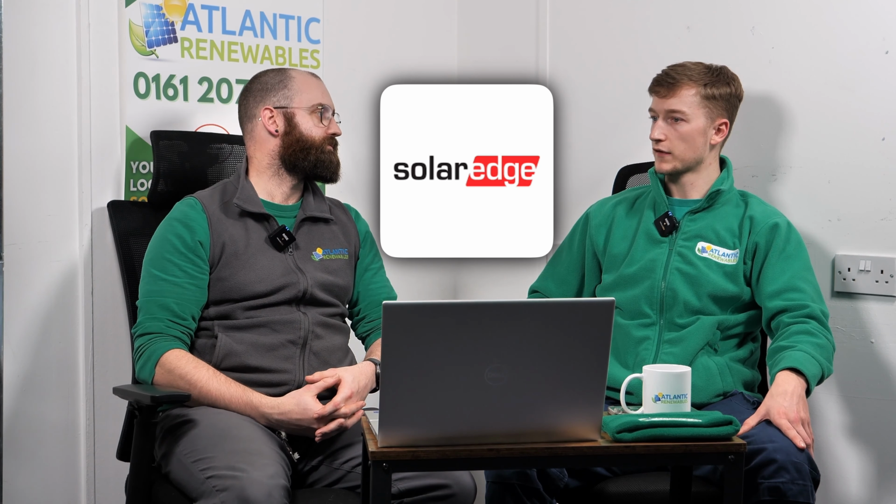I prefer the SolarEdge system. Definitely, if you've got shading problems, it's best to optimise those panels and have the monitoring. The monitoring is important. Unless we were doing, for example, a 10 or 11 panel system and only one of the panels was really affected by shade due to a little chimney or a flue or something, one Tigo could make sense. But typically if there's a big tree or a chimney or even a neighbouring building, then SolarEdge just makes the most sense. It's efficient with the DC.